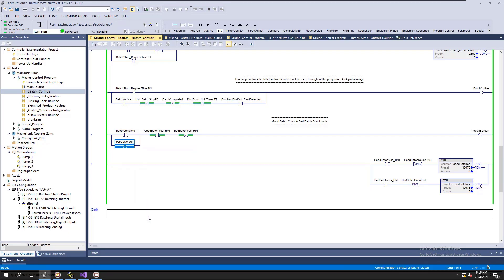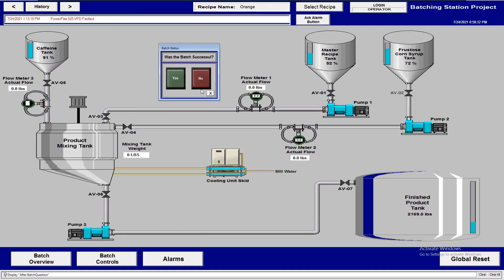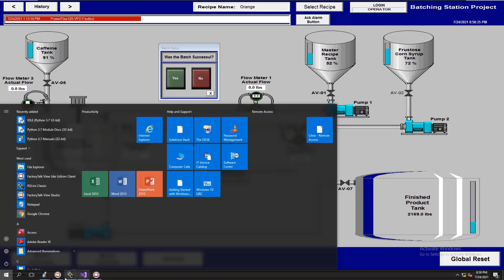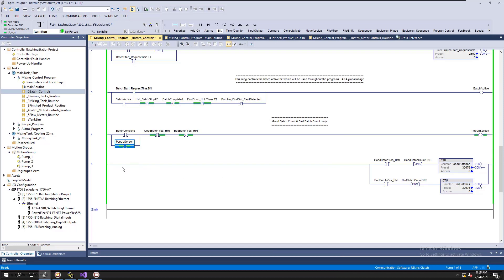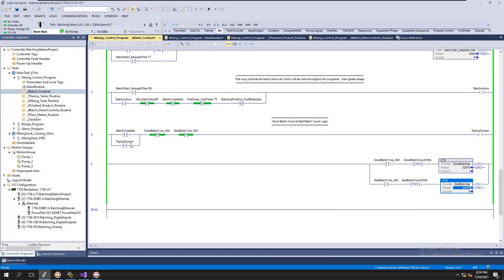I'm going to do a batch pop-up right here and pop this up, then come over here — you see this pop-up happened. Now if I hit yes, keep in mind, I want you to look in the code: if I hit yes, it's going to unlatch this bit, unlatch this seal-in circuit, and also count on one of these counters — either a good batch or a bad batch. If I say yes it was a good batch, then I close it, come over here, and it should have unlatched the seal-in circuit and counted a one right here under the batch.